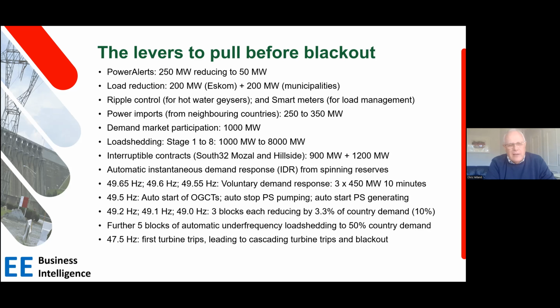If that doesn't help and the frequency drops from 50 hertz down to 47.5 hertz, in other words, a 2.5 hertz reduction, a turbine will start tripping out. And that's what leads to a national blackout, because once a turbine trips out, there's less supply. Now supply starts dropping, and so the imbalance between supply and demand gets even bigger. After the first turbine trips, the next one will trip out in a certain amount of time, and it gets into a cascading situation where all the turbines at the power station trip out, and you have what is called a national blackout. But the thing is, there are all these levers at our disposal.